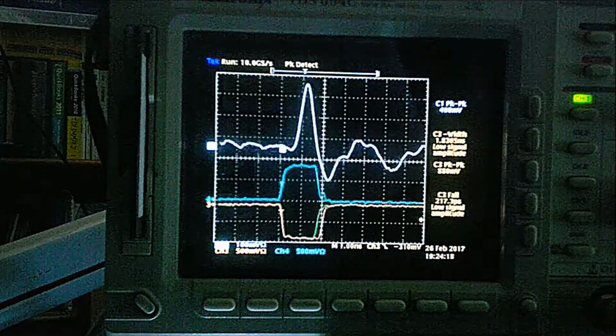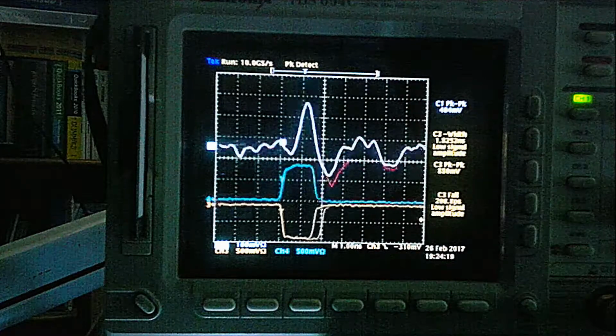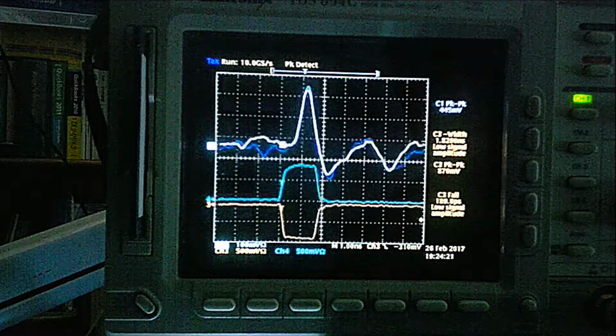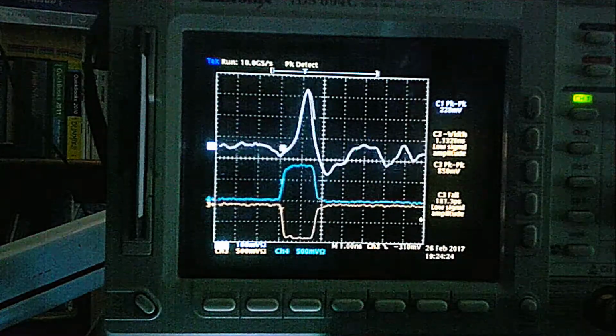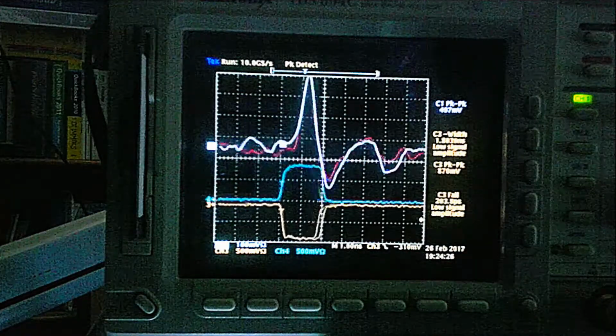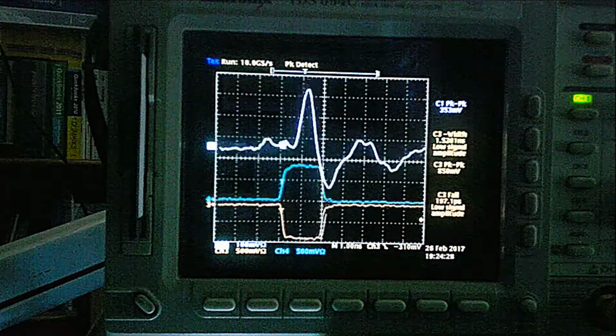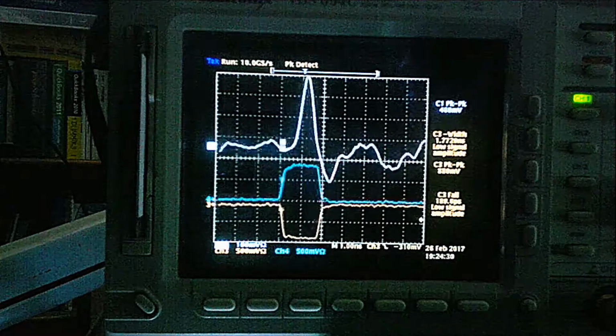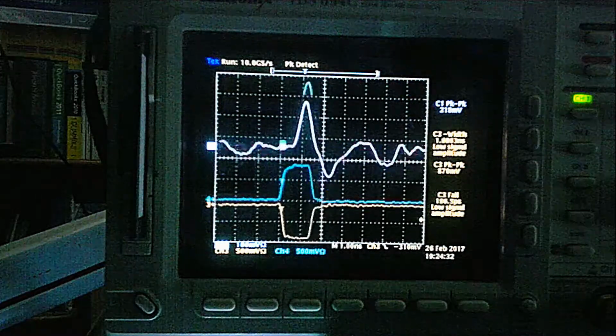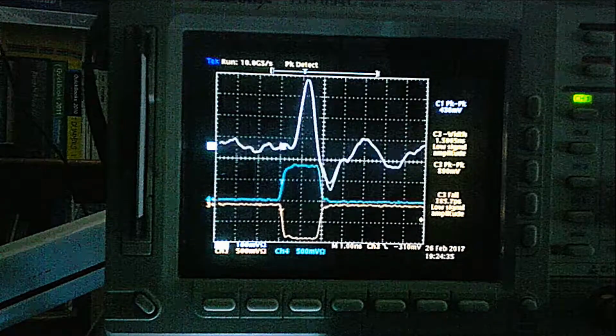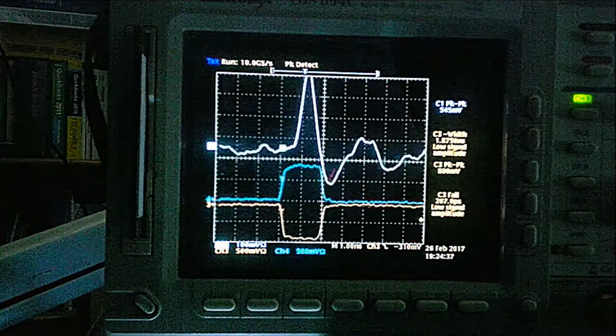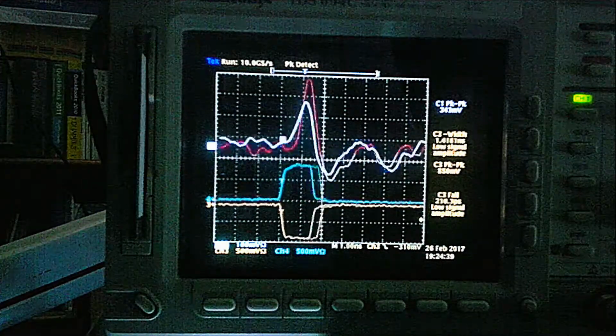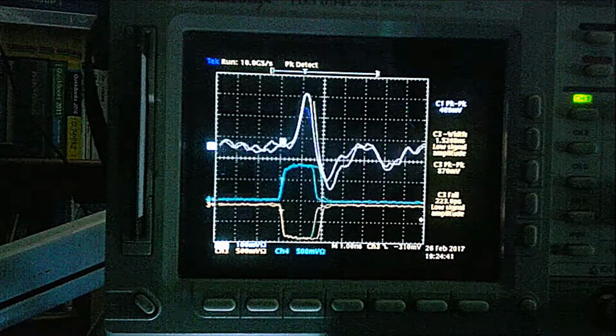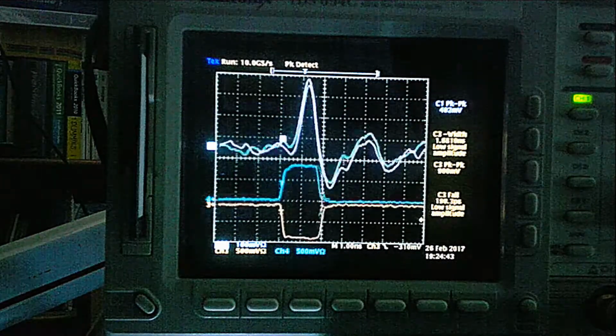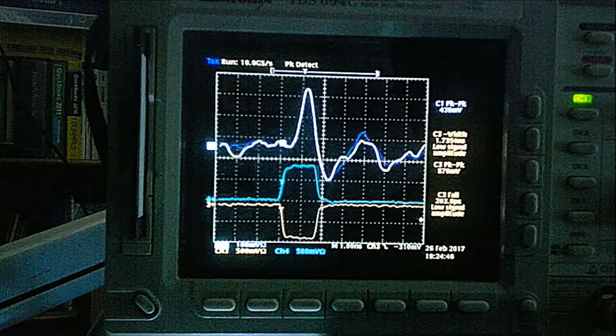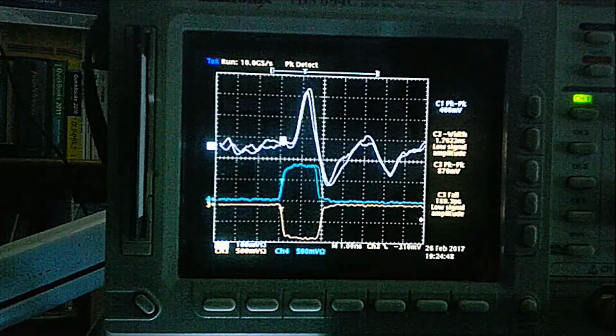This is a revised video showing how to set the discrimination level for the Marina Photonics PV16 amplifier discriminator when used with the Hamamatsu hybrid photomultiplier. The top trace is the output of the Hamamatsu hybrid tube amplified by 60 dB after being split in two. The other half of the signal that's split out is going into the PV16 amplifier discriminator. We're seeing the top trace is single photon events, and the bottom trace is the output of the PV16.